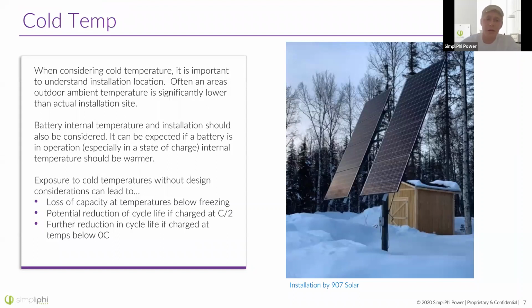When considering cold temperatures and where you're physically located, your environmental conditions, you also want to think about the actual installation site. Some people see our temperature range of 32 to 120 for charging temperature and think, oh man, last winter it dropped to 20 degrees once here, I can't install my batteries there, that's going to void my warranty—and that is not the case.